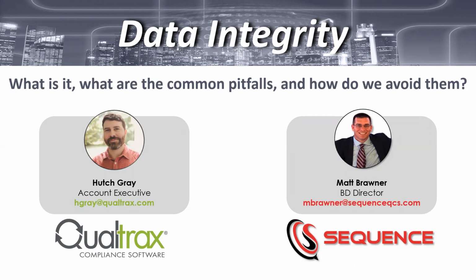An example, and again, this may not be the right solution for your business situation, is that if there are not adequate data integrity controls around how a system is storing data, maybe you can write data in real time and immediately to another more secure location that does have the data integrity controls. That's just an example of how you might deal with an older instrument.